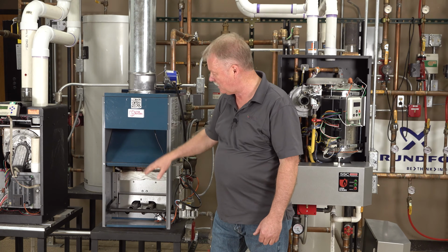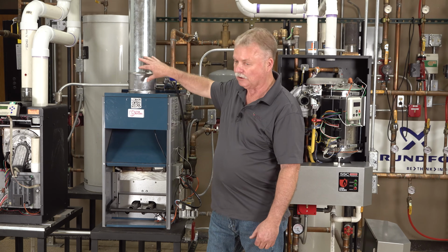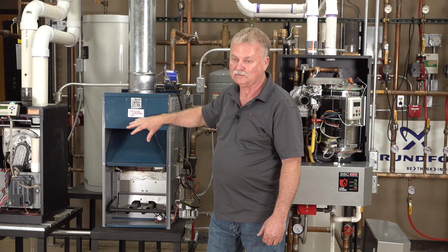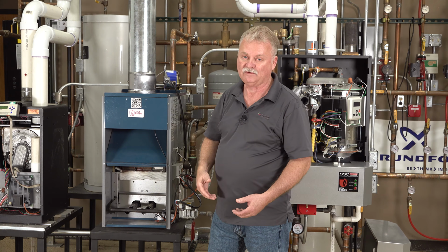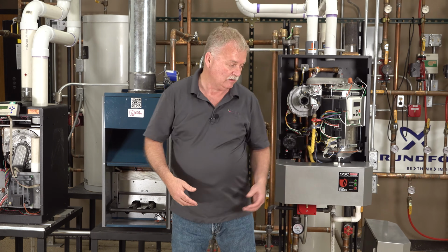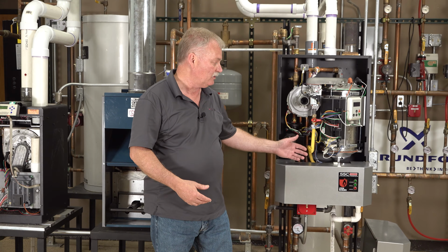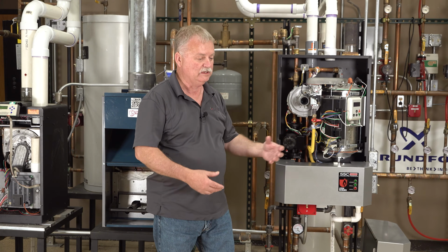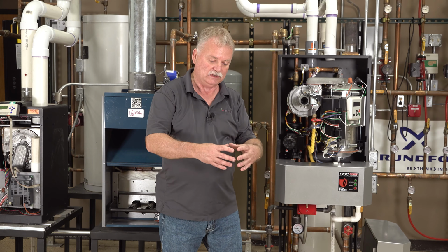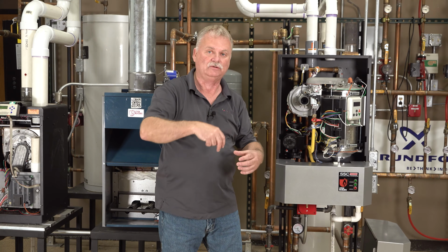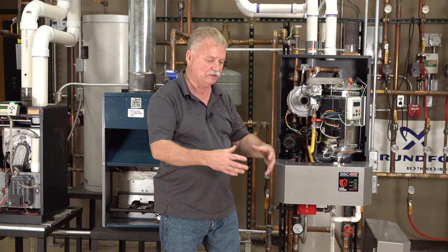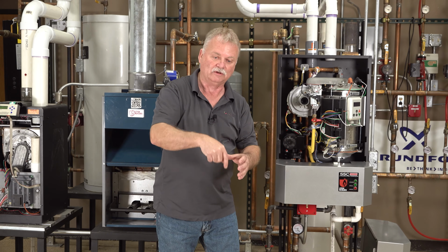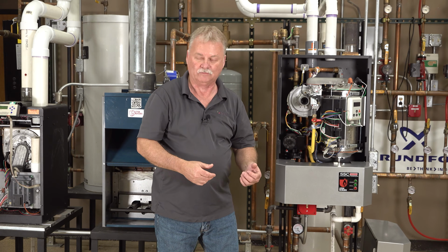Got a couple burners in the bottom, cast iron block in the middle, normally vented up a regular chimney or flue in the 80% efficient range. Nowadays, we are going to more high efficiency equipment. Over here is a typical high efficiency fire tube type boiler. By fire tube, what it means is basically there's tubes in the boiler and the fire is in the actual tubes. If you were to open this boiler up, you'd see basically like a 5-gallon bucket with a bunch of straws. The straws are where the fire goes, so it's called a fire tube boiler.